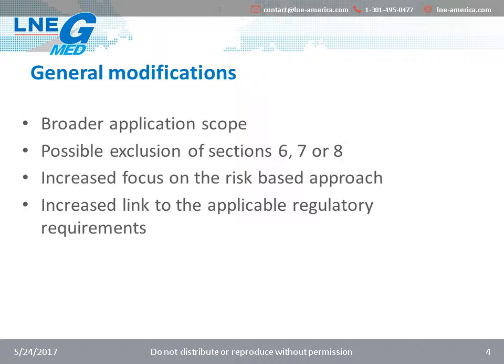With the same goal in mind, the standard now allows an organization to exclude sections 6, 7, or 8, where it was only section 7.3 before. This also means that if an organization relies on ISO 13485 certification within its supplier control process, they will have to look closer at the certification scope. Last but not least, there is an increased focus on risk management and the applicable regulatory requirements, both of which are found in sections related to supplier control.